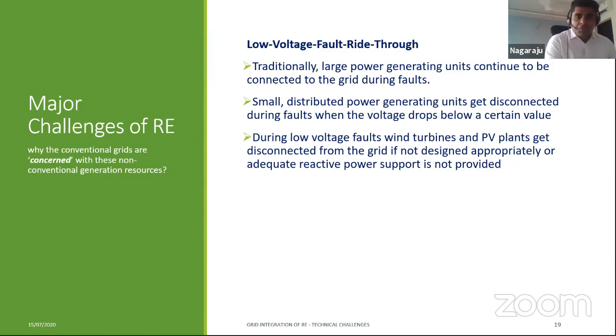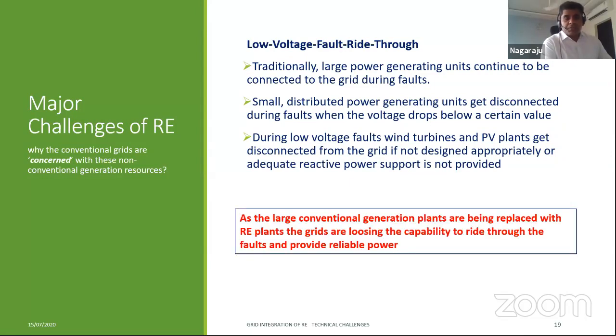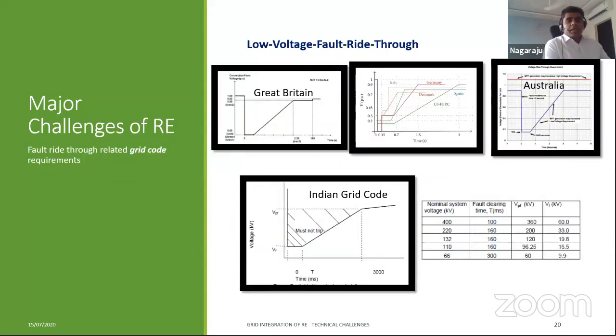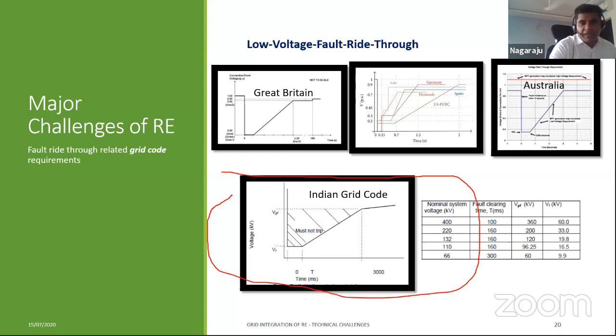The issue with renewable energy sources interfaced by power electronics is that the machines get disconnected themselves when the voltage falls below a certain value. Grids don't want that to happen. That is the challenge. The tripping was an inherent design within the inverters previously because of the component tolerance levels. But now the manufacturers are coming up with innovative solutions to tackle this issue so that they don't get disconnected. They use techniques such as crowbar systems and diverting the rotor currents to ride through. So what are the grids asking across the world? Again, it's too much information, so let us first stick to the Indian grid code here. What the grid is asking is, on the x-axis we have time and the y-axis is the voltage.